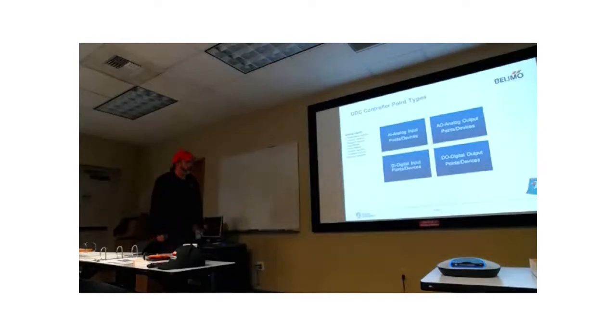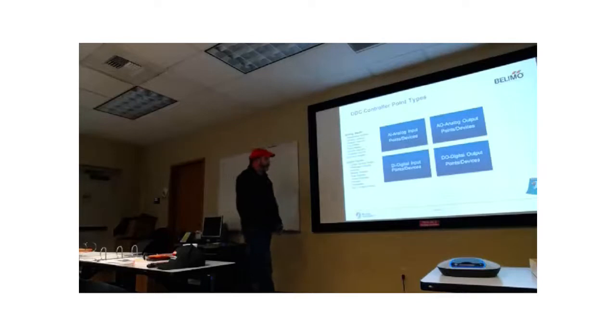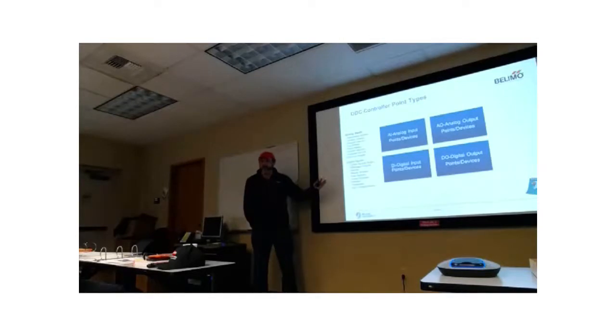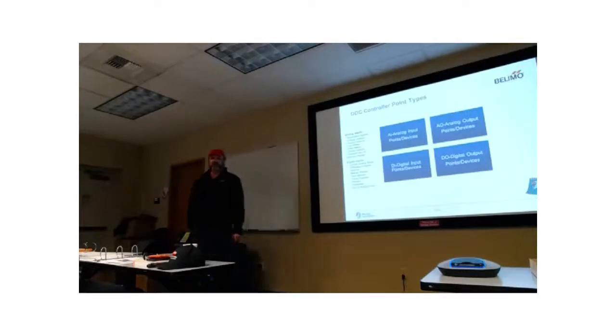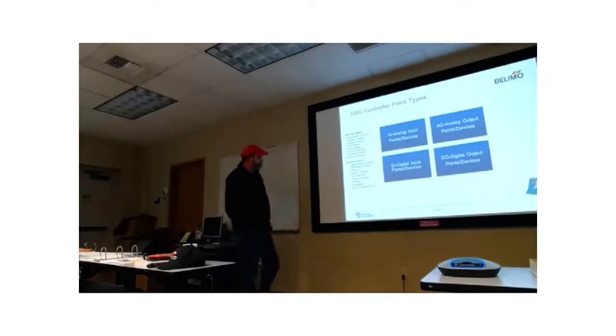Digital inputs - this would be most commonly like a freeze stat on an air handler. That's a digital input. Current sensing relays, flow switches, proof switches, things like that - it's just a contact closure that says something has happened. I have flow, I have fire, something like that. I'm freezing, something like that.